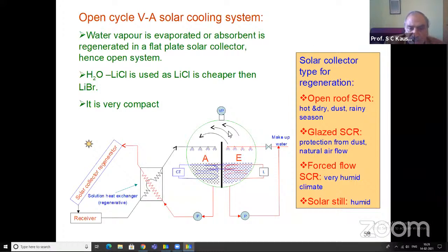Both are working at the low pressure, which is being maintained with the help of the vacuum pump. So it is a low pressure vessel where water is being sprayed. Now water is being sprayed, and this latent heat of vaporization will come from the air which is to be cooled. This is the load. So the water being sprayed is vaporizing because of the sensible heat, as room air is being circulated. Unvaporized water is being collected here, and then it is again pumped to the makeup water. So this is the evaporator chamber.